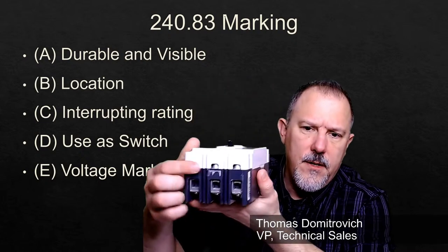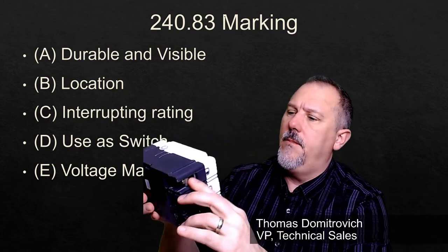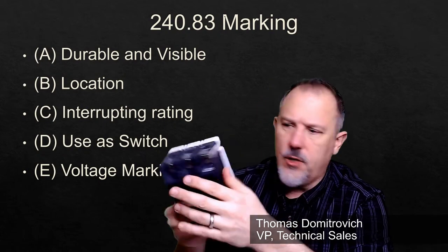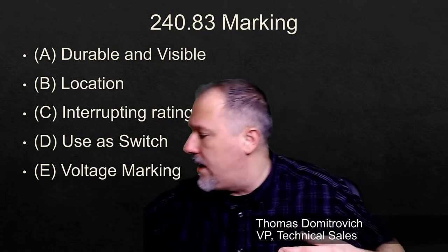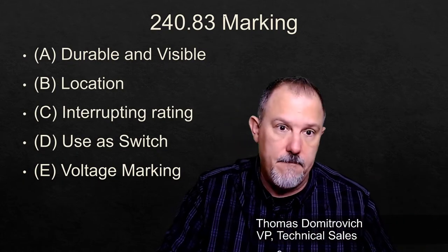This circuit breaker has lugs on one side and has lugs on the other side. So you would probably put this in a motor control center, because this is an HMCP. This is a standard breaker. This could mount on the bus inside of a panel board, right? So they're just designed differently, and the mounting mechanism used to install it inside of a piece of equipment will vary. And you could buy these with different lugs and different kits to go into different equipment.